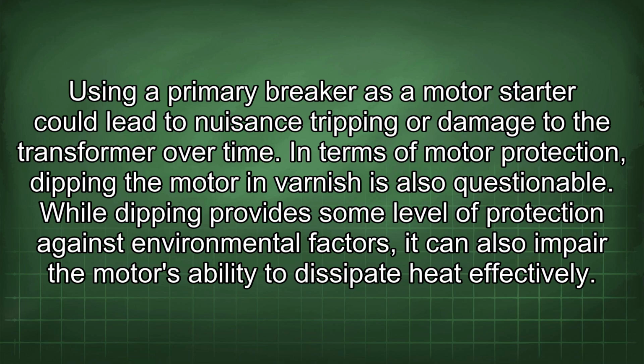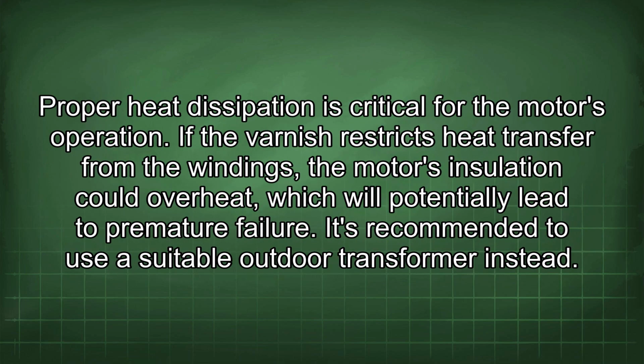In terms of motor protection, dipping the motor in varnish is also questionable. While dipping provides some level of protection against environmental factors, it can also impair the motor's ability to dissipate heat effectively. Proper heat dissipation is critical for the motor's operation. If the varnish restricts heat transfer from the windings, the motor's insulation could overheat, which will potentially lead to premature failure. It's recommended to use a suitable outdoor transformer instead.